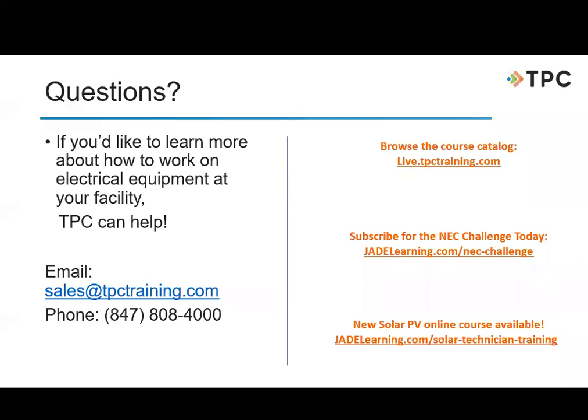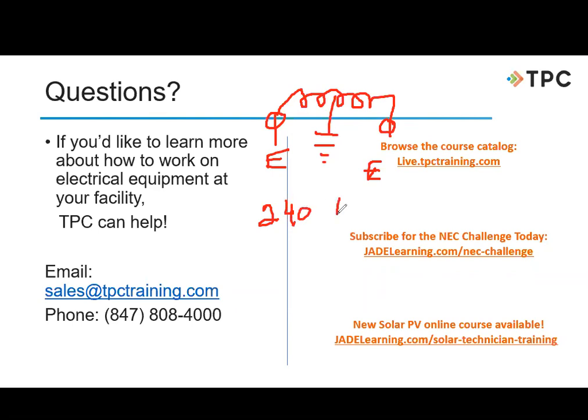Well, two-phase was not used pretty much at all, because I want you to think about this: if we only have one transformer and we have single phase, we do have two ends of that transformer. So we do have two energized conductors there. Single phase really gives me two energized conductors, and then my neutral would be right in the middle. And so we can get 240 volt single phase, but it's really giving us two energized conductors.